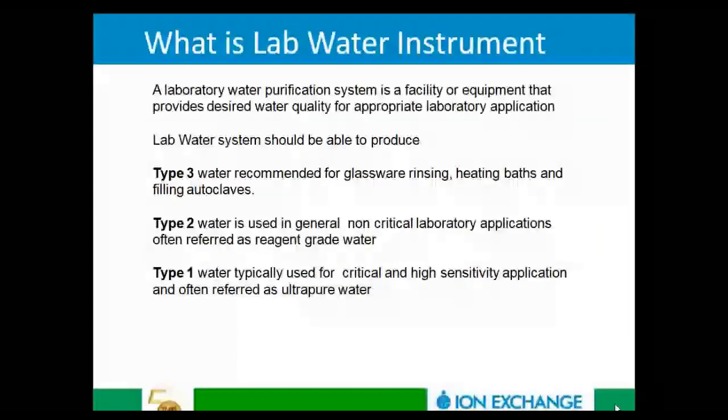So what is this lab water instrument? Simply, a laboratory water purification system is a facility or an instrument that will deliver the desired water quality for the desired application. The point to be noted here is the desired water quality for the desired application, which clearly states that different laboratory applications need different qualities of water.